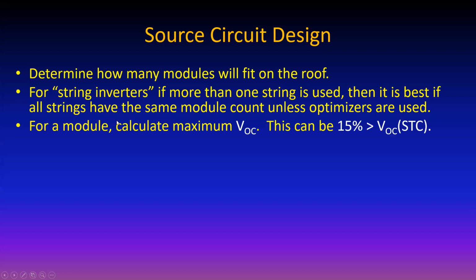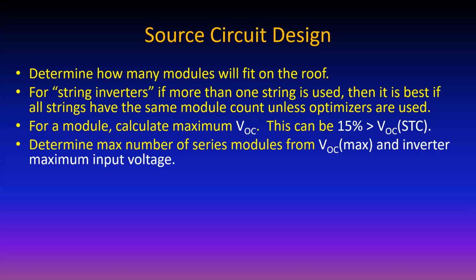Okay, for a module, you need to calculate the maximum open circuit voltage. And since open circuit voltage is temperature dependent, you need to use the temperature coefficient for the module that is on the data sheet. It can be as high as 15% higher than the standard test condition, 25 degrees C. So it's a good idea to do the calculation. But again, this is normally done by a computer program. And then by doing that, this determines the maximum number of series modules, because the inverter has a maximum input voltage. Some are 600 volts, some are 1,000 volts. So you need to know that information about the inverter. Okay, it used to be 600 was it, but now since about 2014, we're allowed to have 1,000 volt DC strings up on the roof.